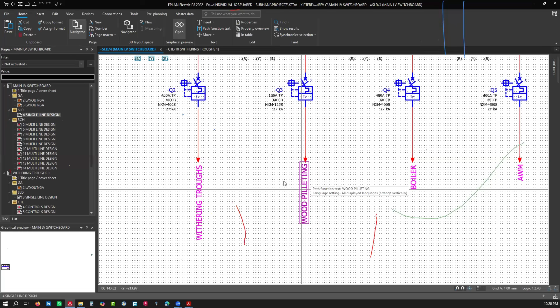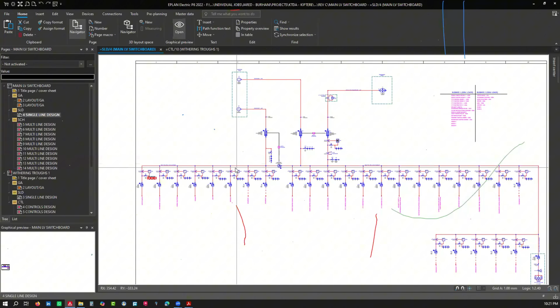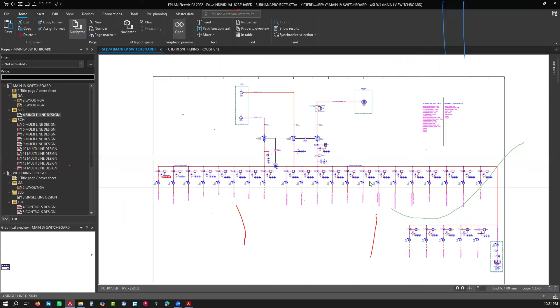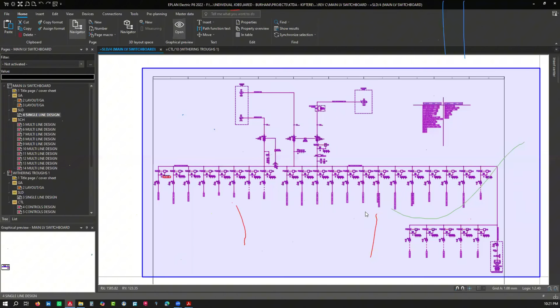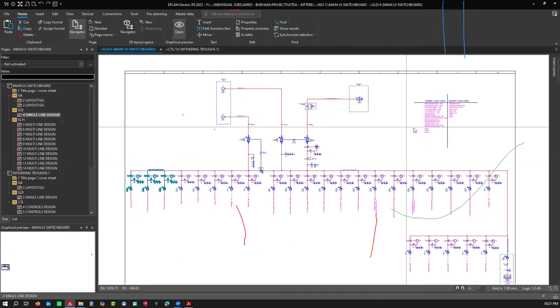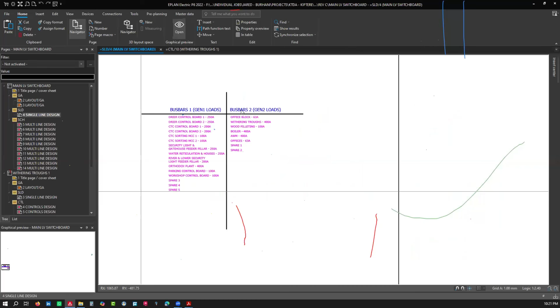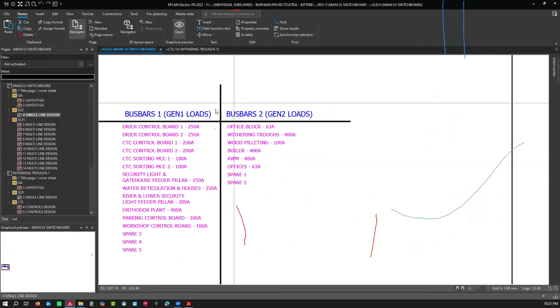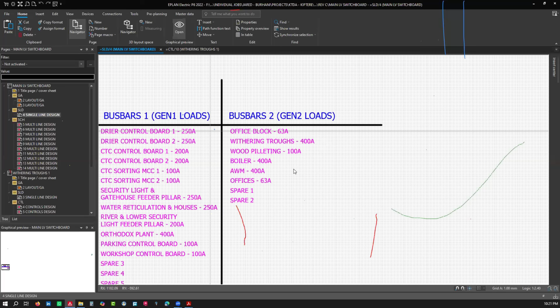Once you do this single line diagram, any engineer describing the system on site, if there are faults, or maintenance going on or downtimes, someone can just check the drawings and maintain the system. It's easier for me to do power reticulation in a single line diagram. But the technician in the workshop will not actually use this directly; only experienced ones will, because we come up with a schedule.